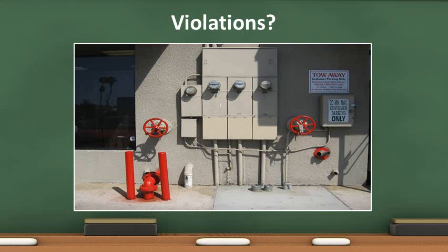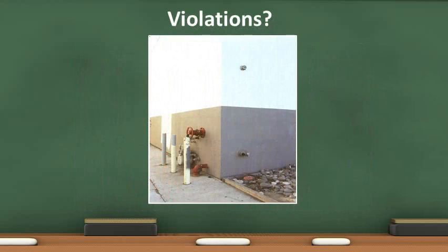And what are the violations in this photo? The FDC is missing caps. There is no sign for area covered by the valves or the FDC, and the chains and breakaway locks are missing. And what violations do we have here? Look on the wall and on the ground above and below the FDC. The fire alarm bell cover is on the ground and the caps are missing from the FDC.